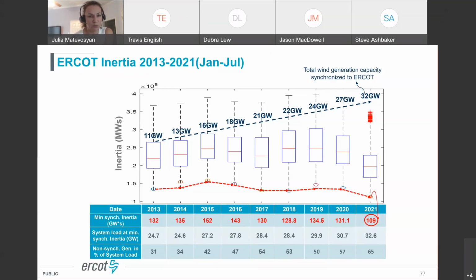One outlier was March this year, where we hit 109 gigawatt seconds of inertia, and we think that maybe it's not as influenced by the number of inverter-based resources on the grid as much as by consequences of the February event, where some synchronous generation was on maintenance after the event, and so less of it was available and inertia went down. So we'll keep monitoring this trend and see what happens next spring, because inertia kind of goes low in spring and fall nighttime when wind is high and load is low. Next slide, please.